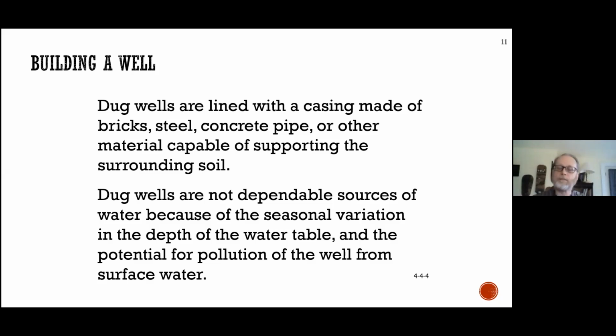In fact, the biggest sort of tragedy in Canadian history that was reported was the Walkerton contamination event 20 years ago, actually almost 21 years ago, May 2000. And there were shallow wells, which were not dug wells, they were bored, but they were only about 6 meters deep. And the surrounding ground around the well had not properly supported the casing.